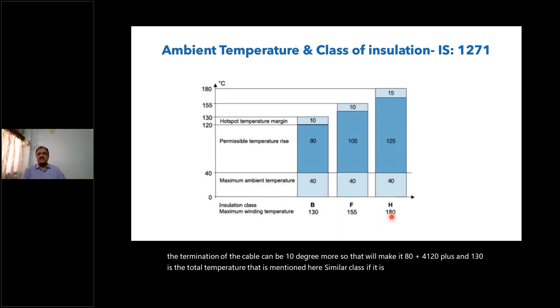But the fact remains that people who go for class F insulation would like to limit the temperature rise to class B level. They will have a class F insulation, but the temperature rise will be limited to class B. This you will find in some consultant specifications. The reason is when you reduce the temperature rise, the life of the insulation will be higher. For every 10 degrees centigrade that is reduced for the motor, the life of the insulation will double. This is an adage available in industry practice.